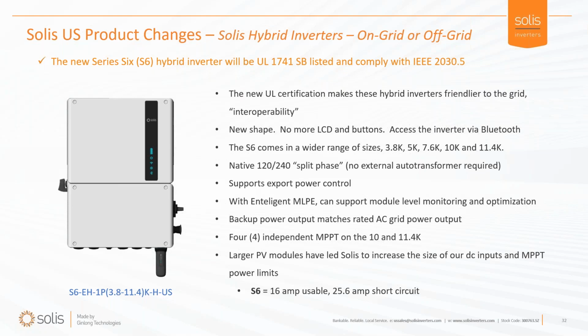So you could actually stack these inverters as well. If you've got a small home 100 amp panel, you could stack two of these and get 96 amps, over 23 kilowatts continuous deliverable to a full 100 amp panel. It's almost like a whole home in a partial home type of solution, where you've broken out your biggest loads into the main service panel, or installed a new smaller service panel and use your old load panel as backup.